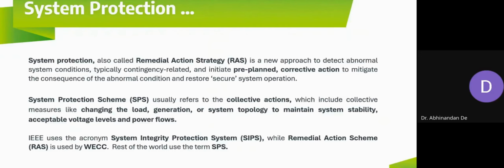These contingency-related abnormal conditions can be taken care of by this remedial action strategy or system protection. What it basically does is initiate a pre-planned corrective action to mitigate the consequence of the abnormal condition and restore secure operation of the system. That is the definition of what a system protection scheme means.